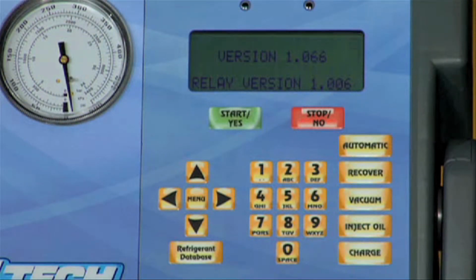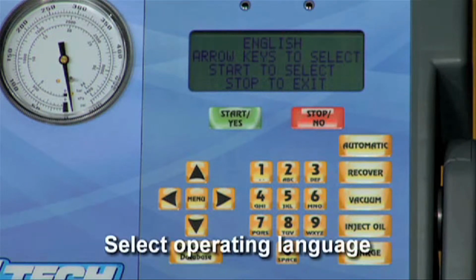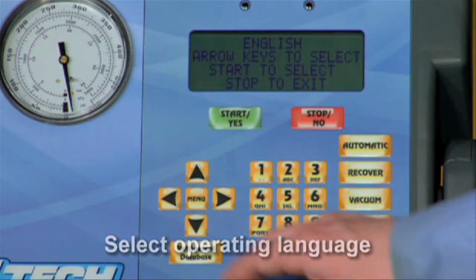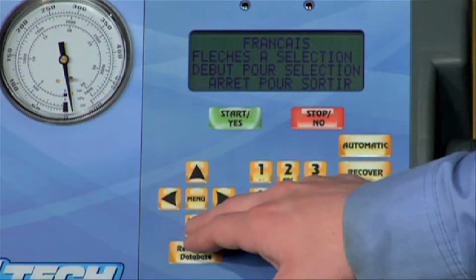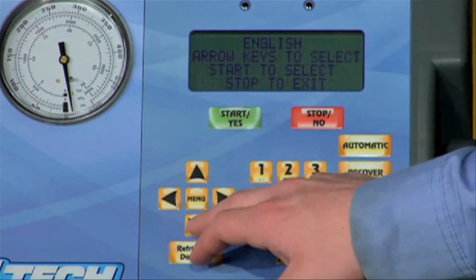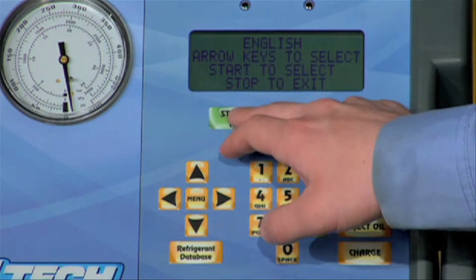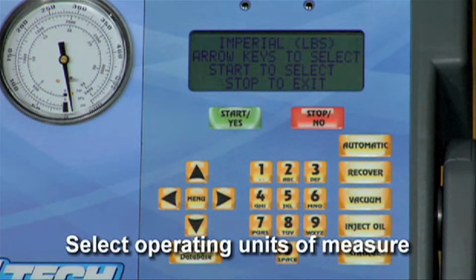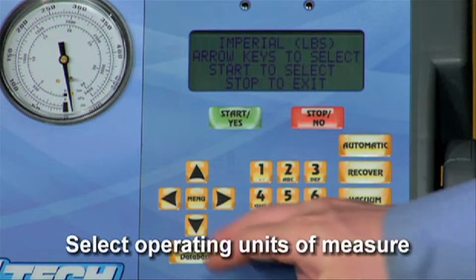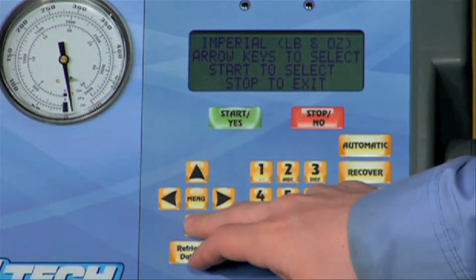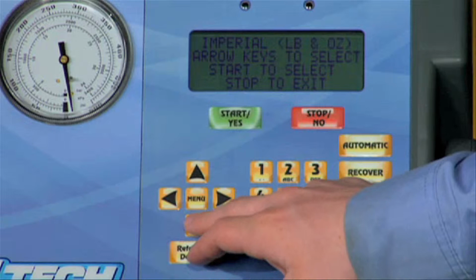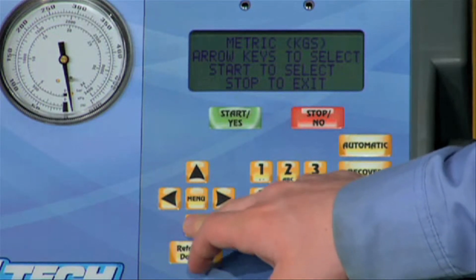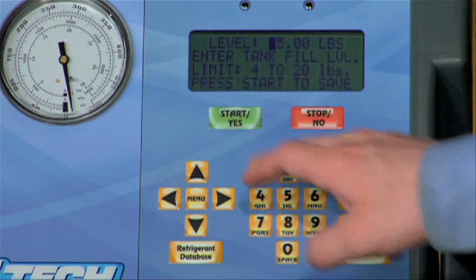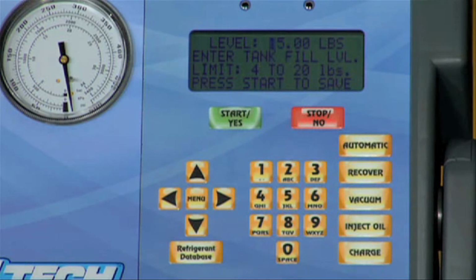front panel. Your first option is to select a text language for the 34788 from one of 3 languages: English, French, or Spanish. Use the up or down arrow key to toggle through the choices and press the Yes key to select the displayed language. You will now choose to have test results displayed in imperial or metric units of measure. The imperial option will display amounts in pounds and ounces, while the metric option uses kilograms. Use the up or down arrow key to toggle through the choices for imperial or metric units. Press Yes to select the operating unit of your choice.